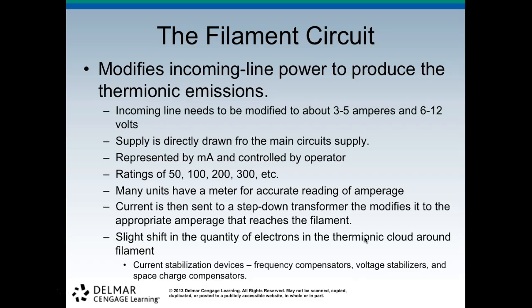So we usually have ranges from 50, and then it goes 100, 200, 300, etc., up to 500. It can go up to 1200 depending on your units. Many units have a meter for accurate reading of amperage, so the current is then sent to a step-down transformer and modifies it to the appropriate amperage to reach the filament. There's a slight shift in the quantity of electrons in the thermionic cloud around the filament, so we put in current stabilization devices such as frequency compensators or voltage stabilizers or space charge compensators.